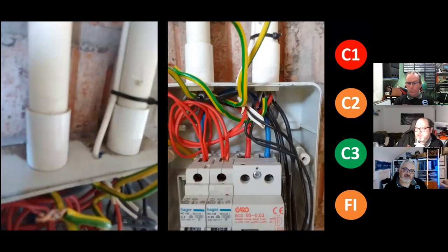We're nearly there. Hooray. Now, John, Jesus. This is one of your ones, wasn't it? No, this isn't one of mine. No, I don't remember this one. Hang on, this is another one sent on Instagram. This is a board that's just been butchered and battered over the years with cables. As you can see, in the picture on the left, someone's running a twin and earth rather than down the conduit, just chopped a hole in the top.